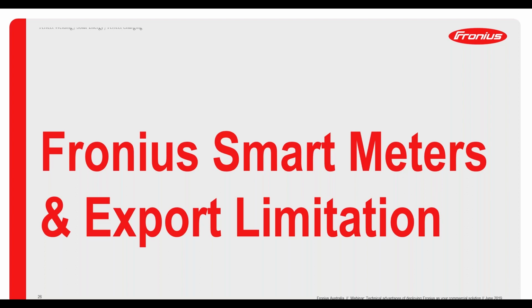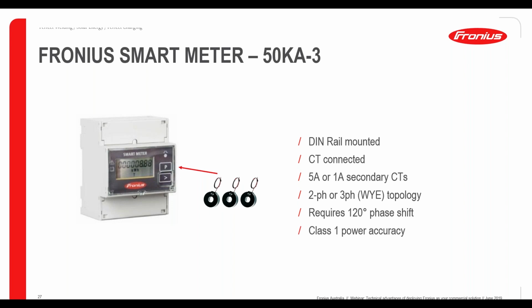This is a typical picture of a Fronius smart meter, 50KA-3. What is interesting about this meter is that it has two typical current input capabilities: 5 amp secondaries and 1 amp. What you've probably met on site will be 5 amp secondaries. We do support what's called a Y measurement topology, so there'll be a typical three-phase, what we see on site. You could also use it for single phase. Be mindful that if used for three-phase, or let's say two-phase, sorry, this meter expects to see a 120-degree shift between the phases, so you can't technically use it with a split-phase or 180-degree split phase systems.